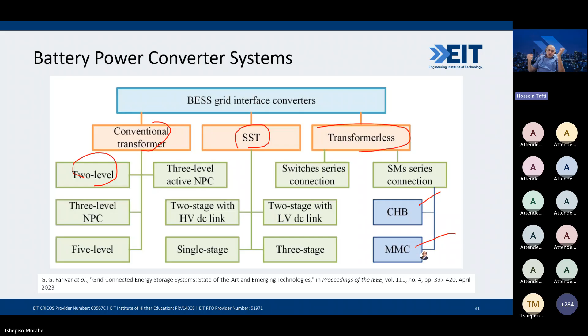For example, if we have relatively low voltages for our battery system, like 700 or 800 volts, we could simply use two-level converters. However, for higher voltages where semiconductor switches such as IGBTs or MOSFETs cannot handle those high voltages, we could go to multi-level converters, such as cascaded H-bridge converters or modular multi-level converters. The main point is that each battery system, based on its voltage, where it's connected, how it's connected, and what features we want from it, could have a selected or suitable power converter.